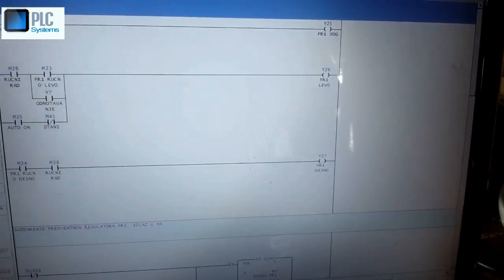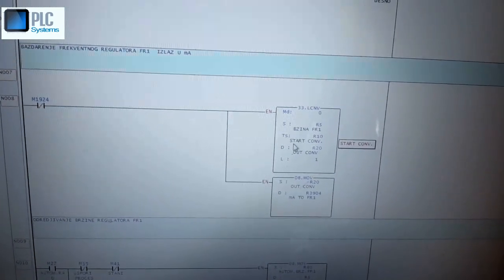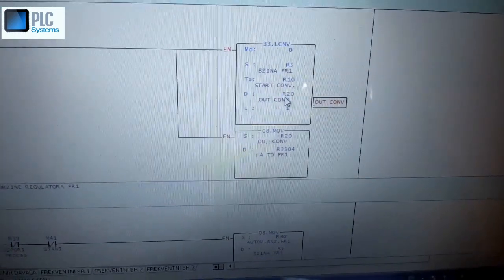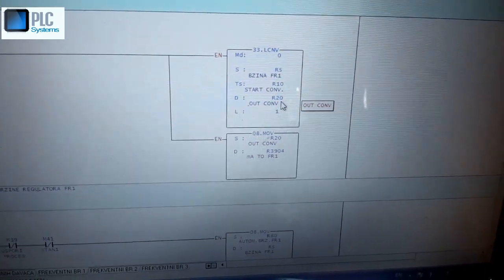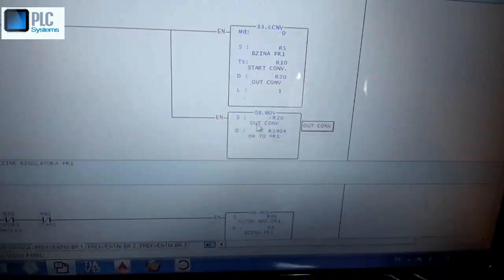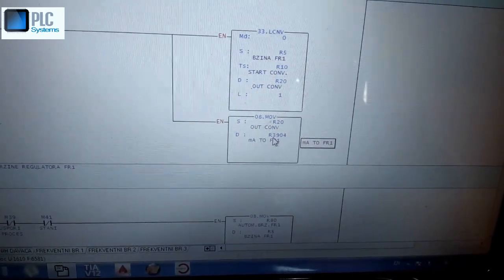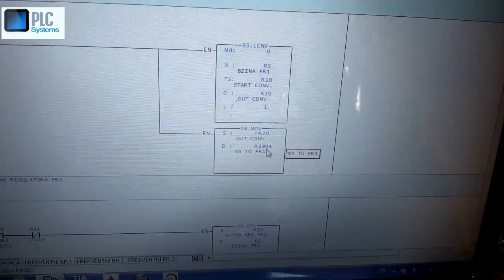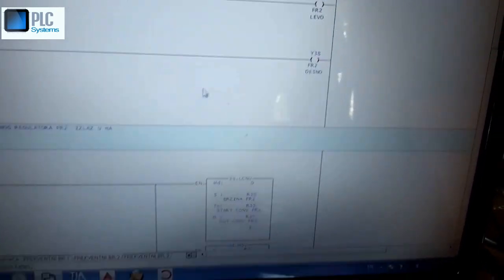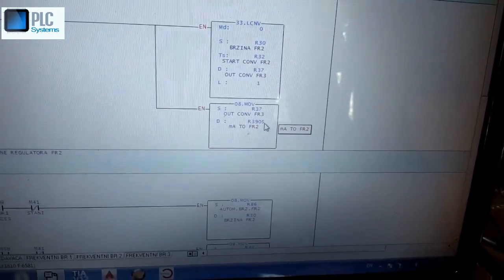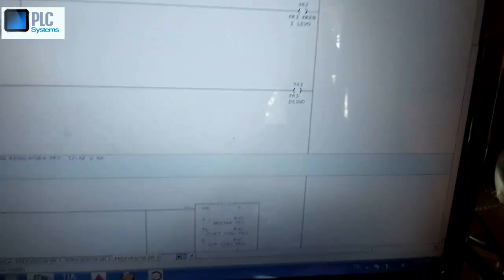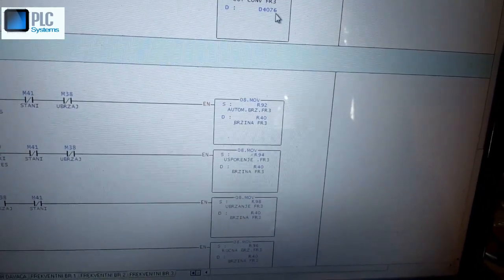The same way to calibrate the speed of analog output — I use the frequency regulator number one and you see. The start registry of conversion is R10 and the conversion variable is R20. I use R20 moved to the analog output registry 3904. Also with analog output registry 3905, and for the expansion unit it is D4076.